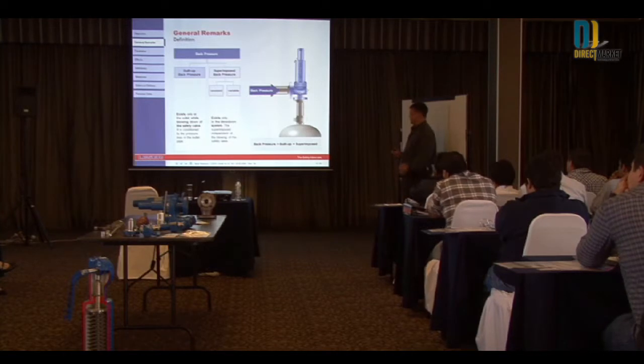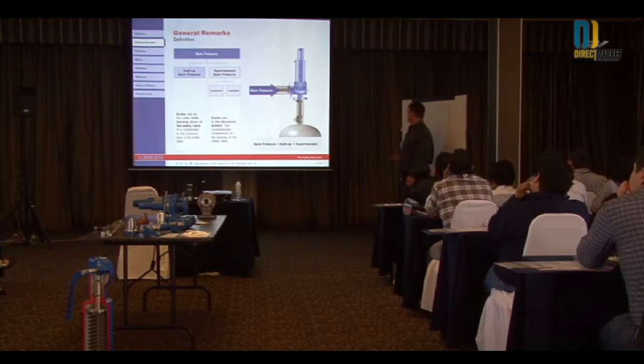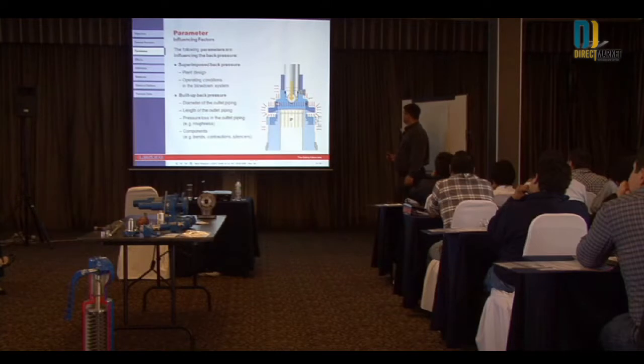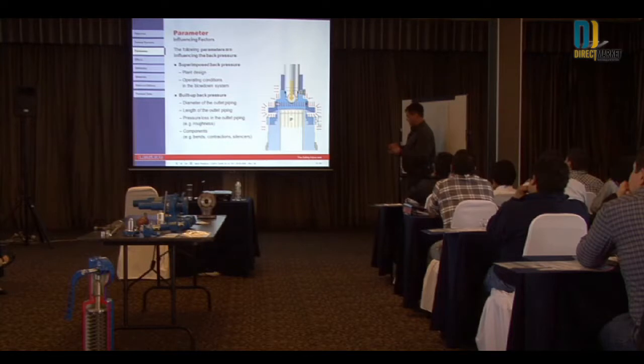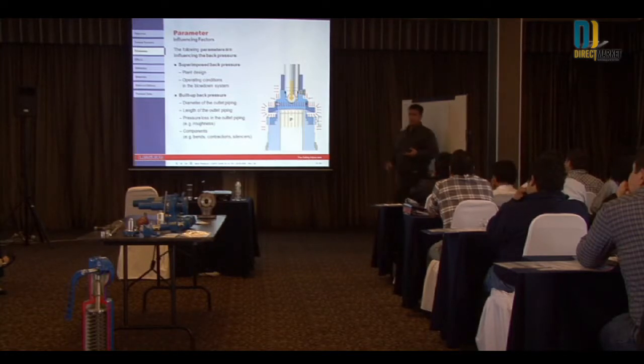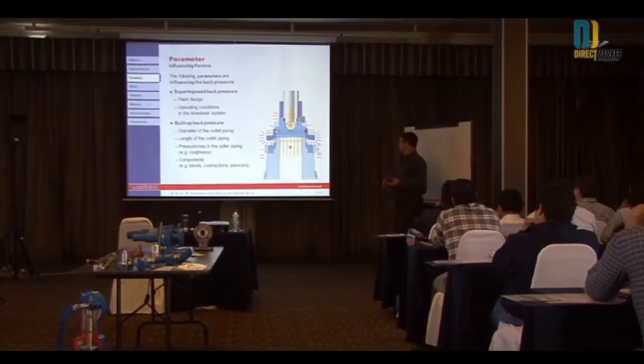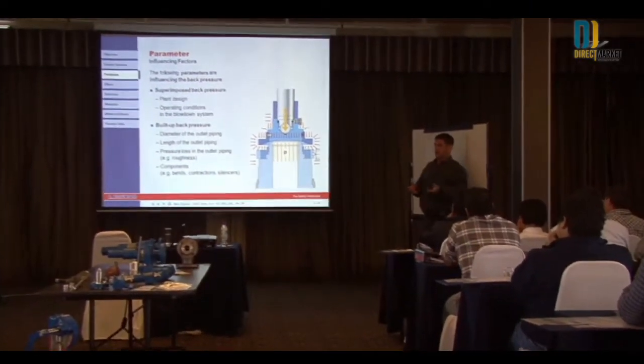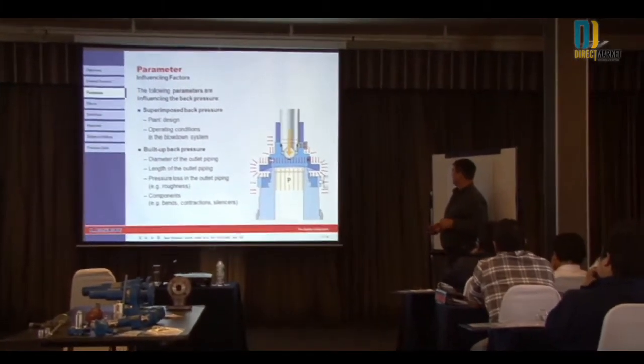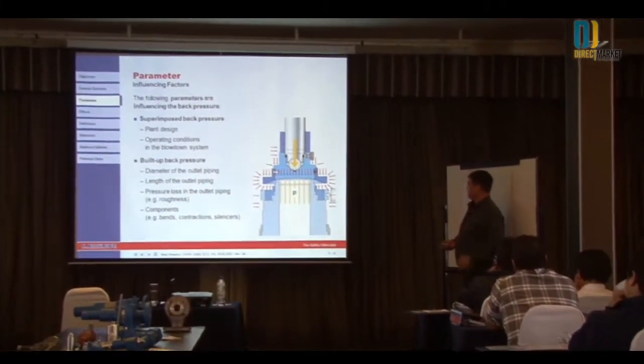It's very important that you compensate for this. The effects that back pressure has on the valve — one component of the valve is the disc. That back pressure is pushing down on that disc, actually holding the valve closed. That's something you don't want, and you want to compensate for it.